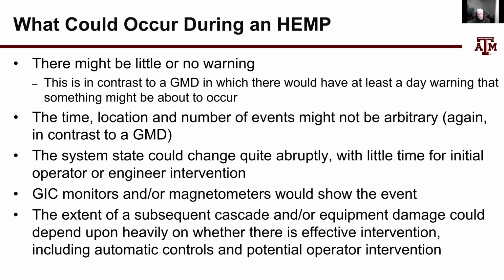The system state, of course, could change abruptly. These events, as I'm showing you based on the DOE guidance, are minutes, 2 minutes in duration. So it's going to change very abruptly with very little time for initial operator engineer intervention. However, your GIC monitors, if you have them, or magnetometers, would show this event.